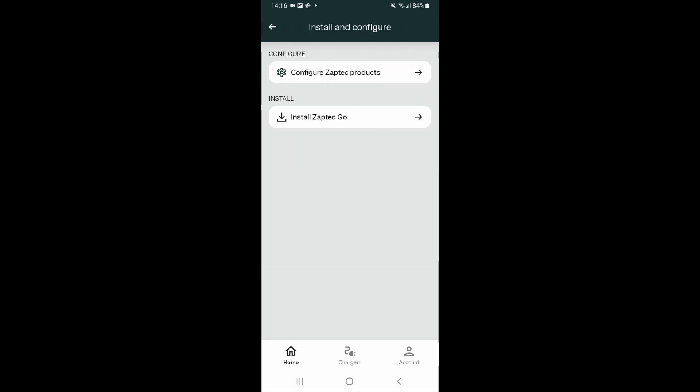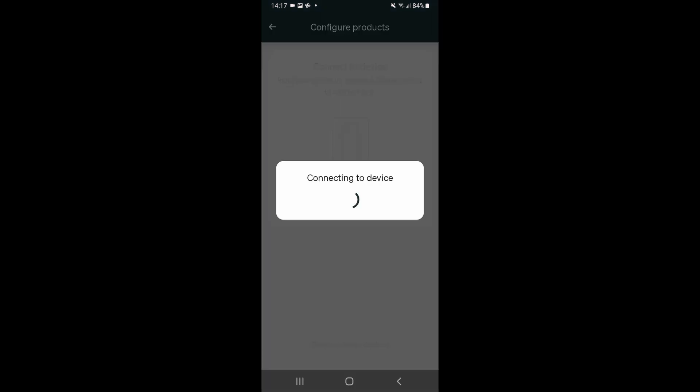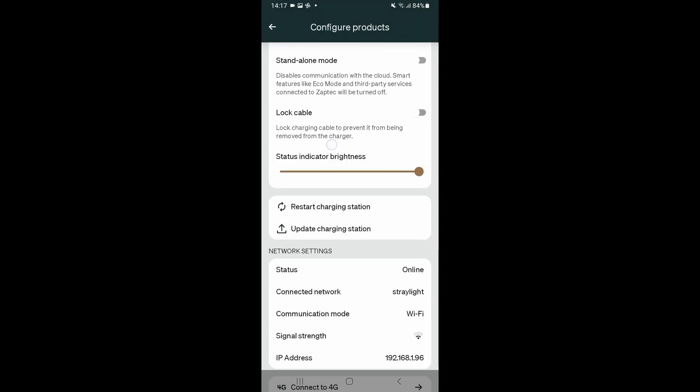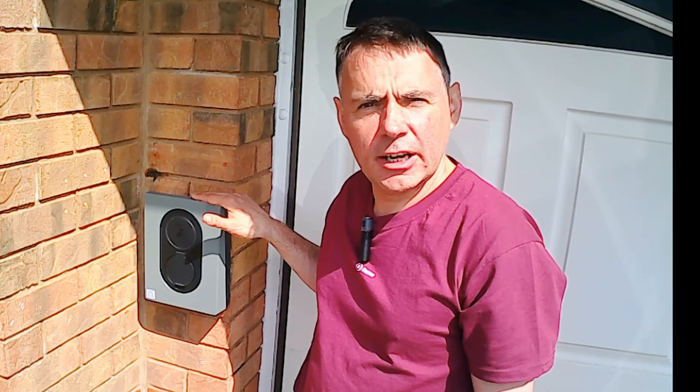The charger should now be connected to the Wi-Fi network. We can check that by going back into 'Configure Zaptec Products' again and connecting again. Now we can see the charger is online, connected, with good signal strength, and we've got an IP address. Our job here is done — the charger is connected, online, and configured. All we need to do is leave the quick product guide with the user.